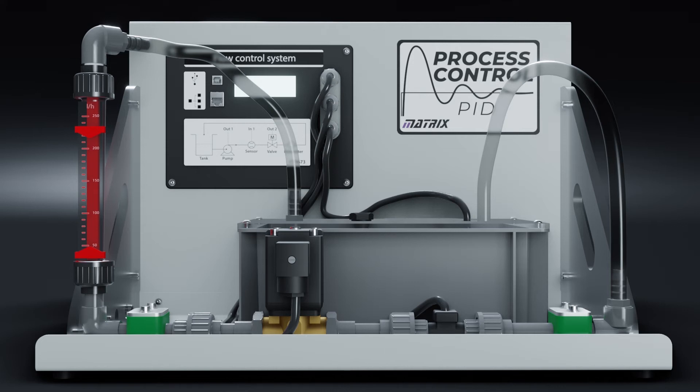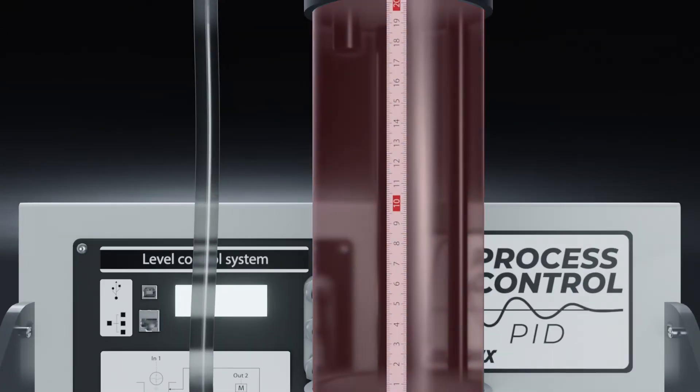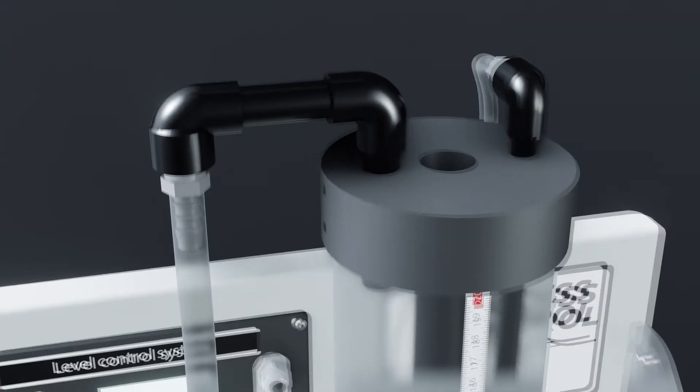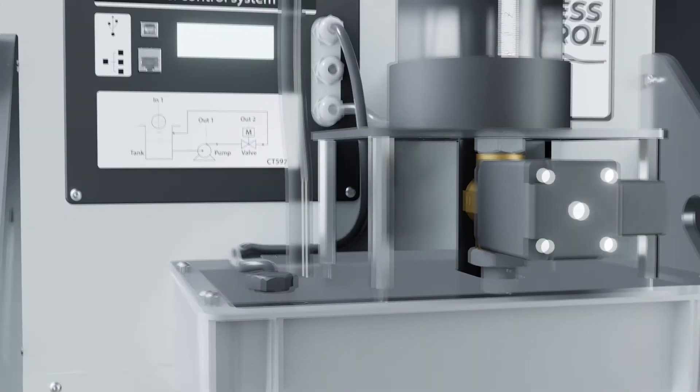The level system consists of a reservoir water tank, a variable speed pump, a pressure-based level sensor, and a clear process vessel with a scale. A proportional valve provides the process vessel drain. An overflow pipe in the process vessel prevents it being overfilled.